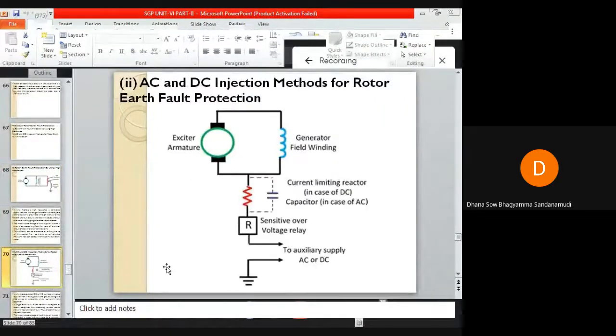Another method is the AC/DC injection method for rotor earth fault protection. In this method, you can inject either AC or DC current into the field winding of the rotor and ground it along with a sensitive overvoltage relay. You can see the sensitive overvoltage relay here. The rotor is grounded with the help of this sensitive overvoltage relay and a current limiting capacitor in the case of AC. Here you can see the auxiliary AC or DC supply. If I am giving an AC supply, I will connect a current limiting capacitor. If I am using DC, I will connect a current limiting reactor. That is why I have shown it here in dotted form.